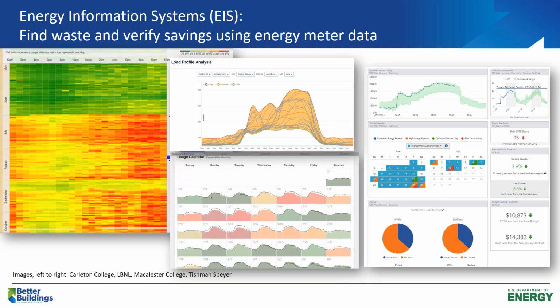In the middle, we have a load profile analysis. This is where you can see for a 24-hour period what your base load is, what your peak load is. In this particular situation on the top, they show a median, a min-max, and this is over, I think, a month period or so. This can be enlightening. You may not know that your building HVAC stays on 3 hours past what you thought, and this can give you a little indicator of that in your load.